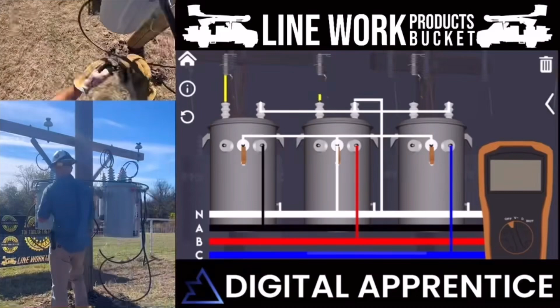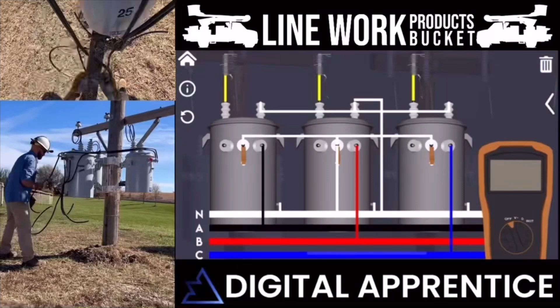Now make sure you check rotation if you ever kill these transformer banks and change out a service, and then you have to go hook it back up with the new service, because you don't want to mess up the rotation to any buildings, because then it'll turn the AC units on backwards. It can turn on heavy machinery backwards and start tearing stuff up, and it's not good.